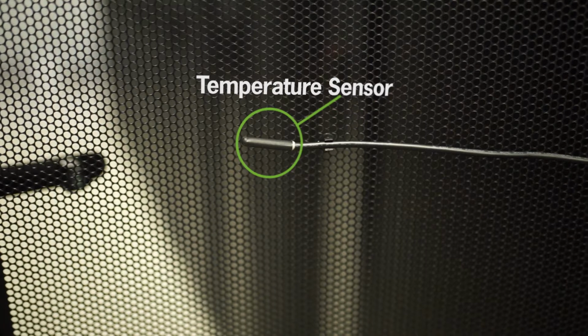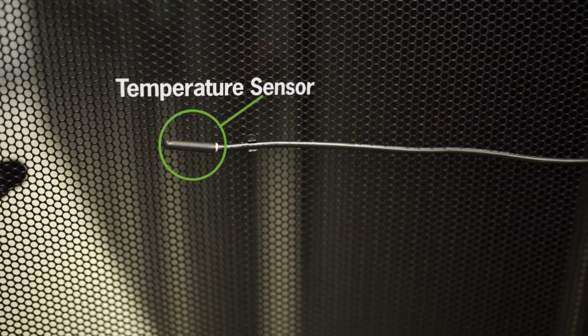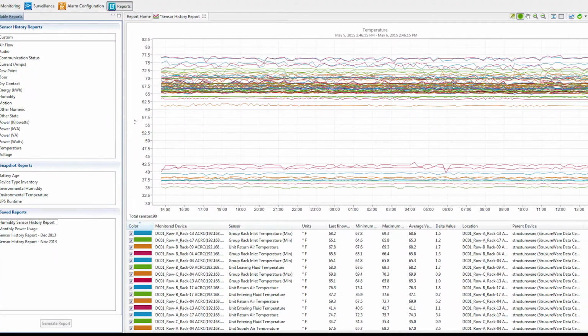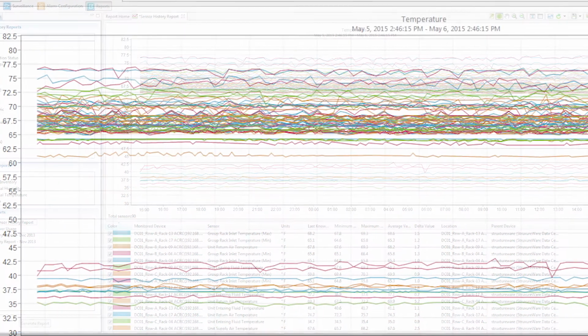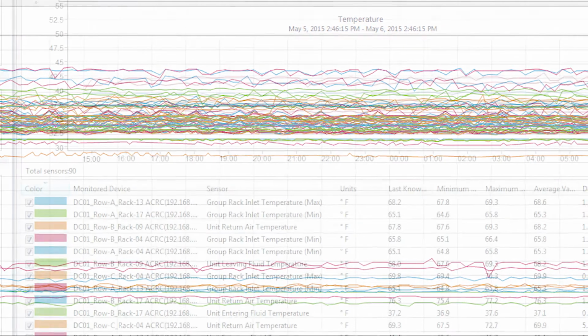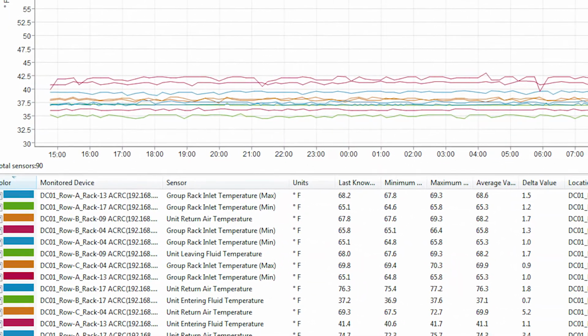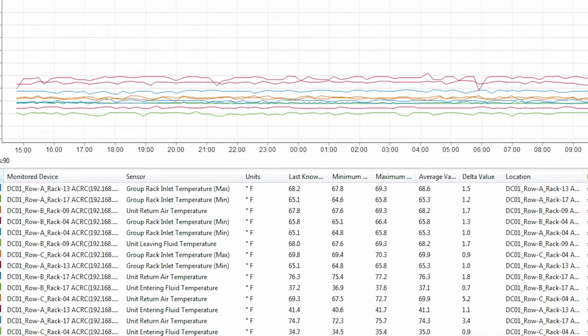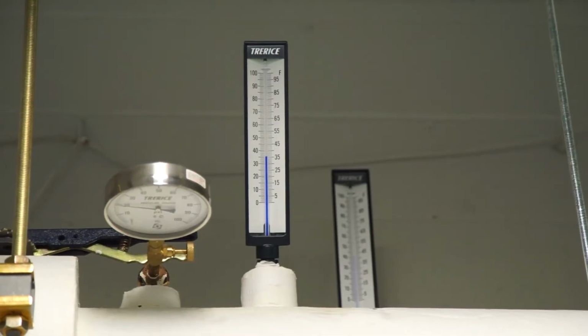Likewise, the cabinets also have their own temperature sensors. Much like a sophisticated thermostat, they analyze the temperature of the air immediate to the cabinet. If the air becomes too warm, the system will automatically adjust the cooling in that area of the room. So while they can function together to keep the whole room cool, regional temperature differences can be addressed by their ability to function independently.